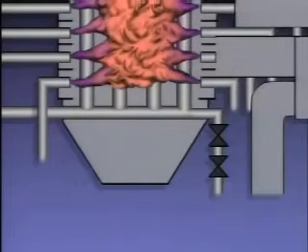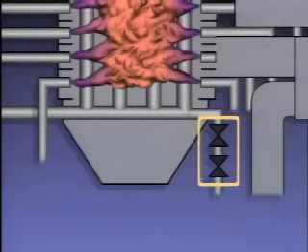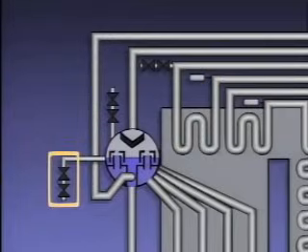Drains, on the other hand, are usually opened only when components are shut down. Drains are used to remove unwanted liquid and are typically located at the bottoms of components. In most cases, opening drains during boiler operation can cause problems. For example, opening a water wall drain while the boiler is operating could upset the natural flow of water through the boiler's water flow path, and the boiler tubes could overheat and rupture.